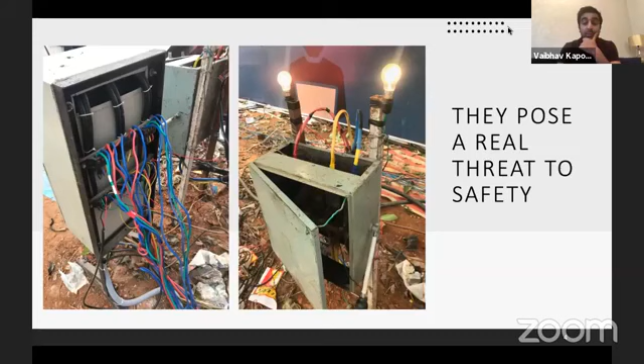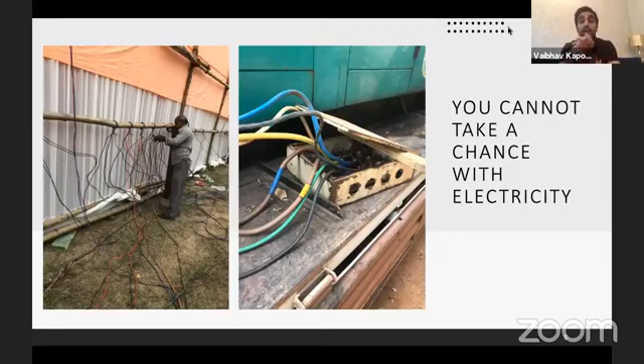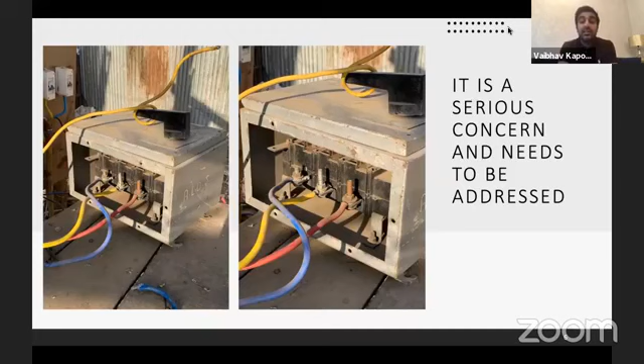In this slide, if you want, we can just cover the whole of power distribution, we don't need to go ahead with the other slides. Again, loose wires, open ends, bucket earths, loose earthing wires, open panels, two bulbs saying the electricity is on, totally open for anybody to come inside, a person doing area lighting. Again, you cannot take a chance with electricity. Changeovers, again, open. It's a serious concern and needs to be addressed.